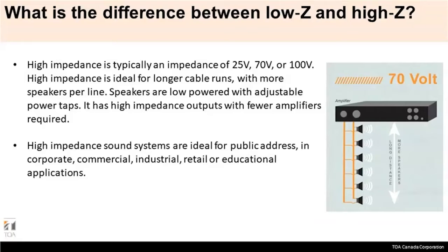Also, for applications that I just mentioned, like schools, hospitals, and commercial and industrial projects, there are n number of speakers, and the cable length is long. The distance of cabling and the speaker placement is widespread. So in that case, it is very useful to use a high impedance or 70 volt system. Technically, it's 70.7 volts that is being used on a wider basis.